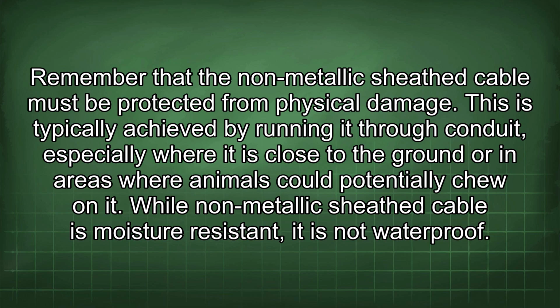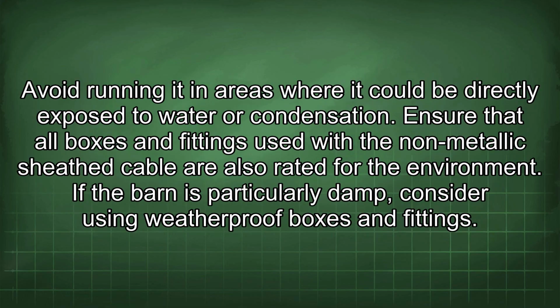Remember that the non-metallic sheath cable must be protected from physical damage. This is typically achieved by running it through conduit, especially where it is close to the ground or in areas where animals could potentially chew on it. While non-metallic sheath cable is moisture resistant, it is not waterproof. Avoid running it in areas where it could be directly exposed to water or condensation.